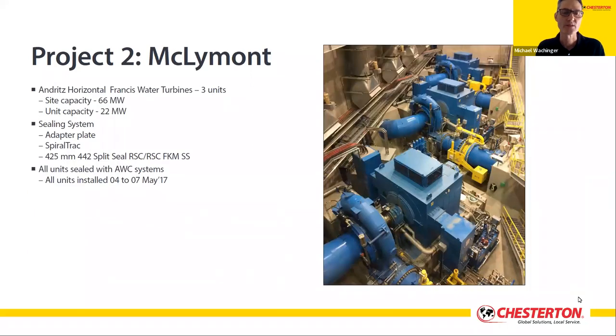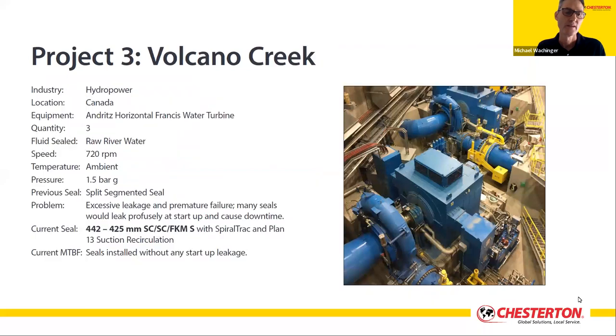With success on unit seven, eventually all nine units at Forest Curve were converted over to a mechanical split seal design with the same result. With the success of Forest Curve, all three units at McLymont were retrofitted with a similar design mechanical seal — again with the same result: no leakage at startup or during running, and minimal flush requirement. Finally, all three Volcano Creek turbines were converted over to a mechanical split seal design. All of these site installations have been running trouble-free to date with no discernible leakage.